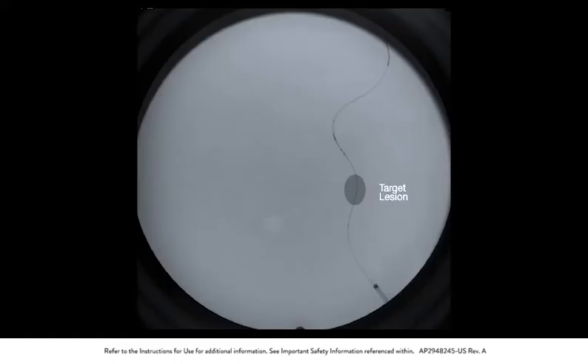Before filtration element deployment, ensure there is adequate distance between the 0.019 inch step on the bare wire and the distal tip of the filtration element to avoid unnecessary contact during the procedure.